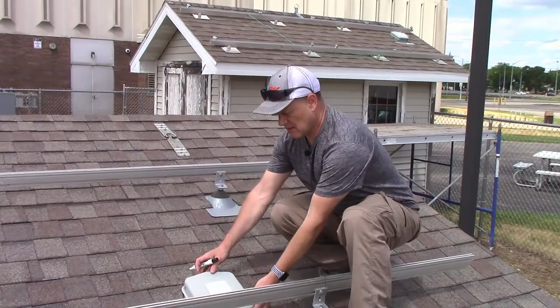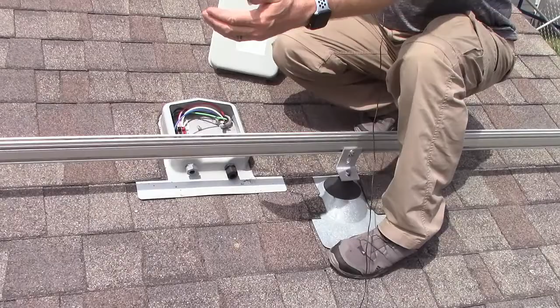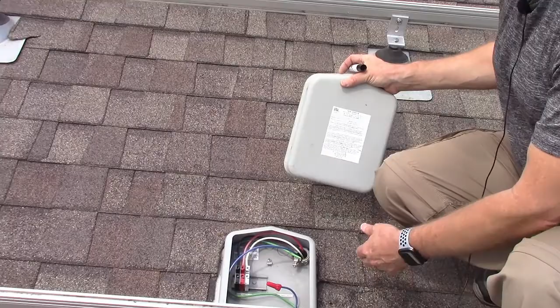Step 4. Map out an efficient module connection arrangement for our PV array. This junction box on the roof is where our conductors from our photovoltaic array will move into the building and connect to the building's electrical system. So this is going to be the connection point that we need to think about as we're laying out our plan for our modules on the rooftop.